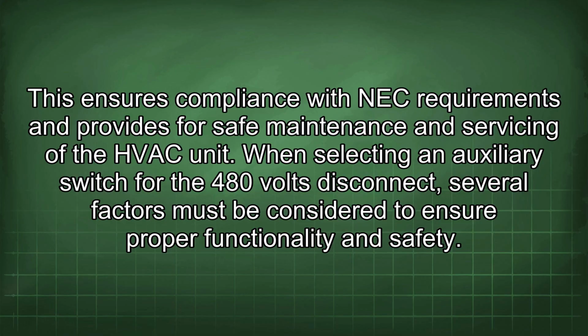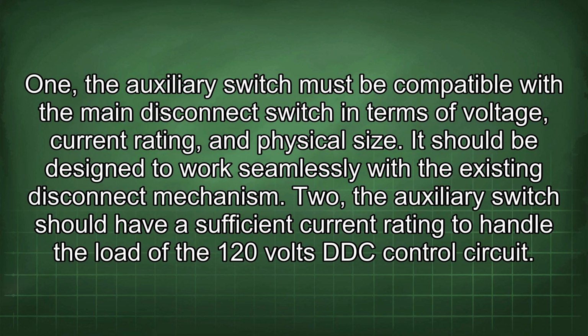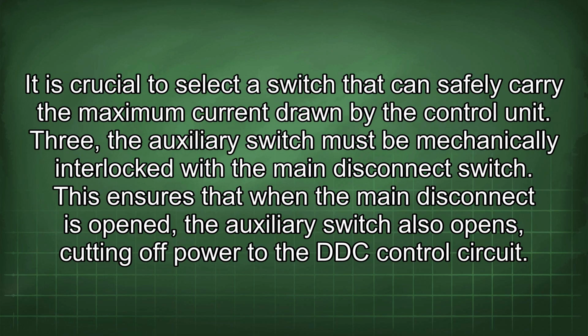When selecting an auxiliary switch for the 480 volts disconnect, several factors must be considered to ensure proper functionality and safety. 1. The auxiliary switch must be compatible with the main disconnect switch in terms of voltage, current rating, and physical size. It should be designed to work seamlessly with the existing disconnect mechanism. 2. The auxiliary switch should have a sufficient current rating to handle the load of the 120 volts DDC control circuit. It is crucial to select a switch that can safely carry the maximum current drawn by the control unit.